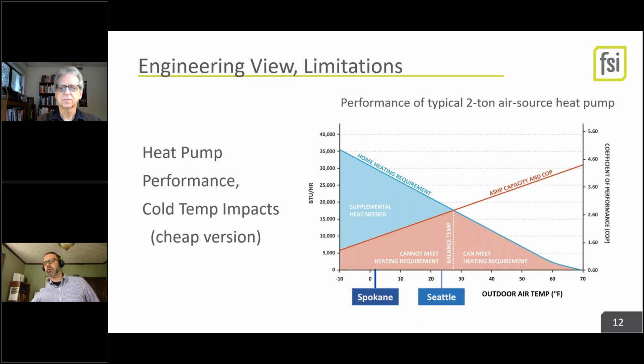But the thing you really get, if you're using a single speed compressor, this is old knowledge in our industry, is that heat pumps won't work in this climate because it gets too cold, and then you have to use electric resistance backup. And for some of those single speed versions we showed you, particularly the PTAC through-wall sleeve unit, yes, particularly for Spokane, you're going to need supplemental heat, and the PTAC will often cut off at 45 degrees and go to electric resistance. True. And that is for single speed compressors. That is still a truth in some of those cases. Let's go to the next slide.